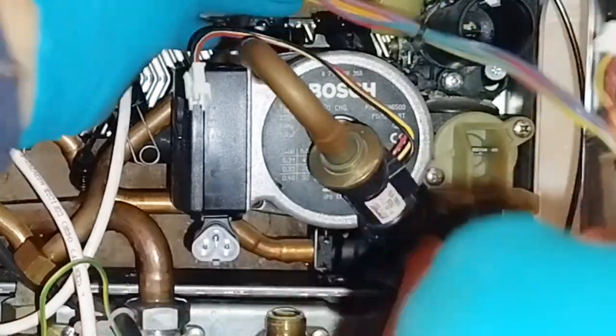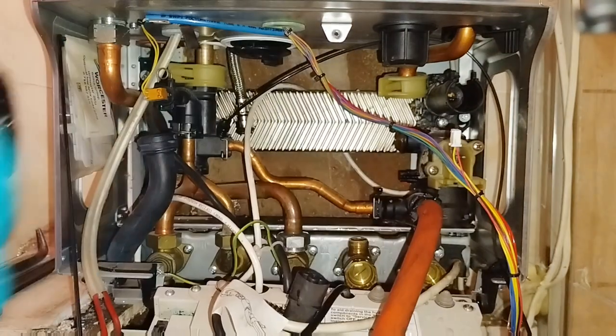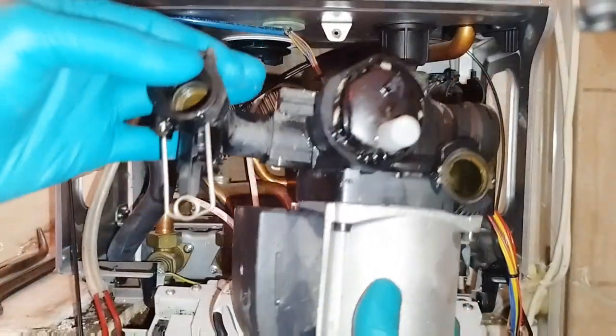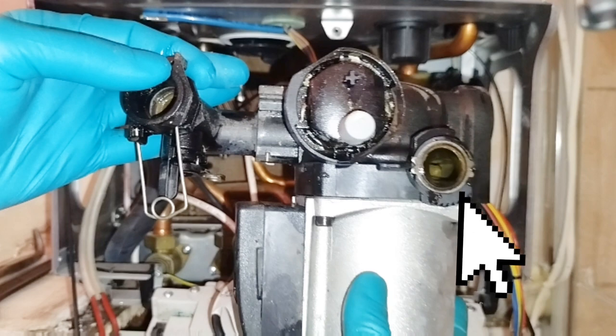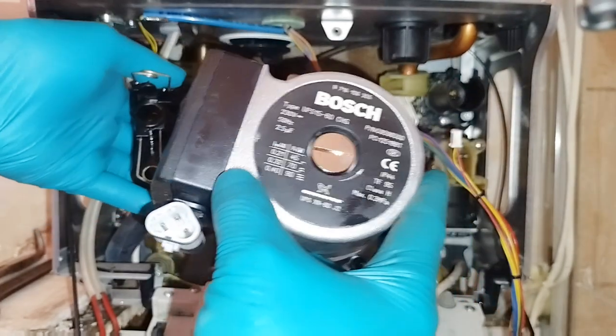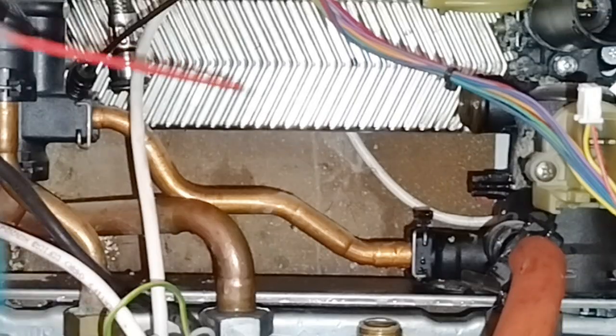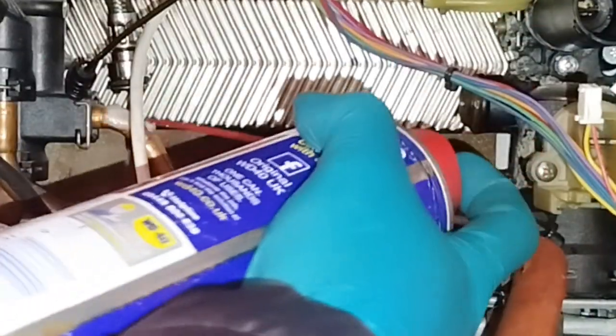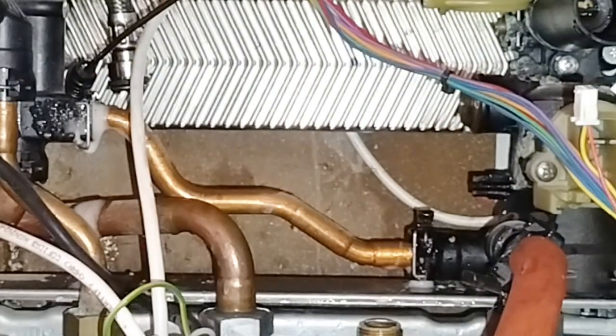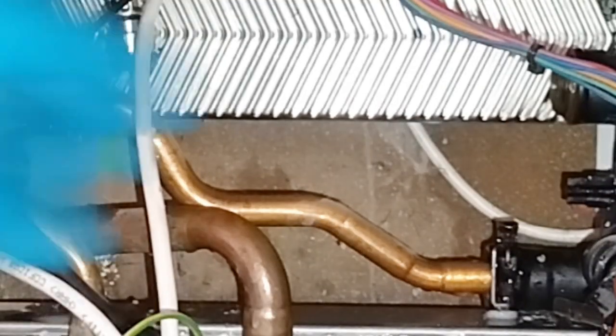Okay, so after the pump's out, have a look at the pump. This is the top, and the washer which sits on the top of the pump, I always replace it and see if anything's damaged or leaking from where it shouldn't be leaking, and with a good inspection you can find out any possible further problems to the pump or this assembly. Alright, so after that, again WD-40 on the bypass pipe just to be able to release it relatively easily when we're removing the return manifold. So this little clip, I pulled it forward in order to release it, so the manifold can come out when we start to wrestle with it again.